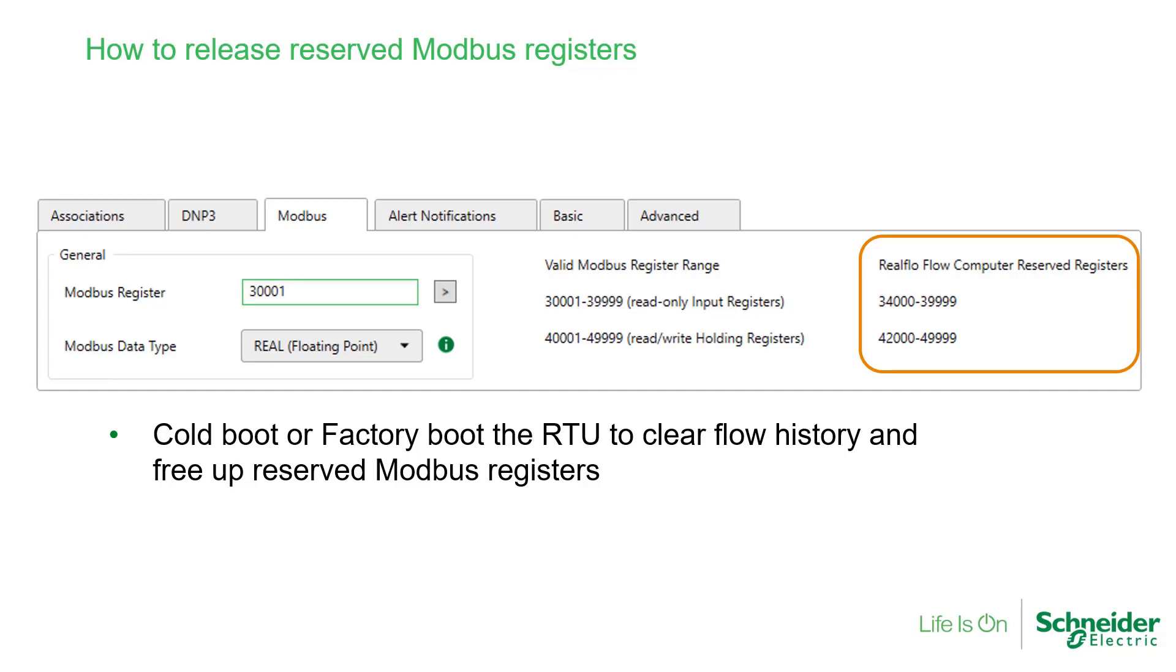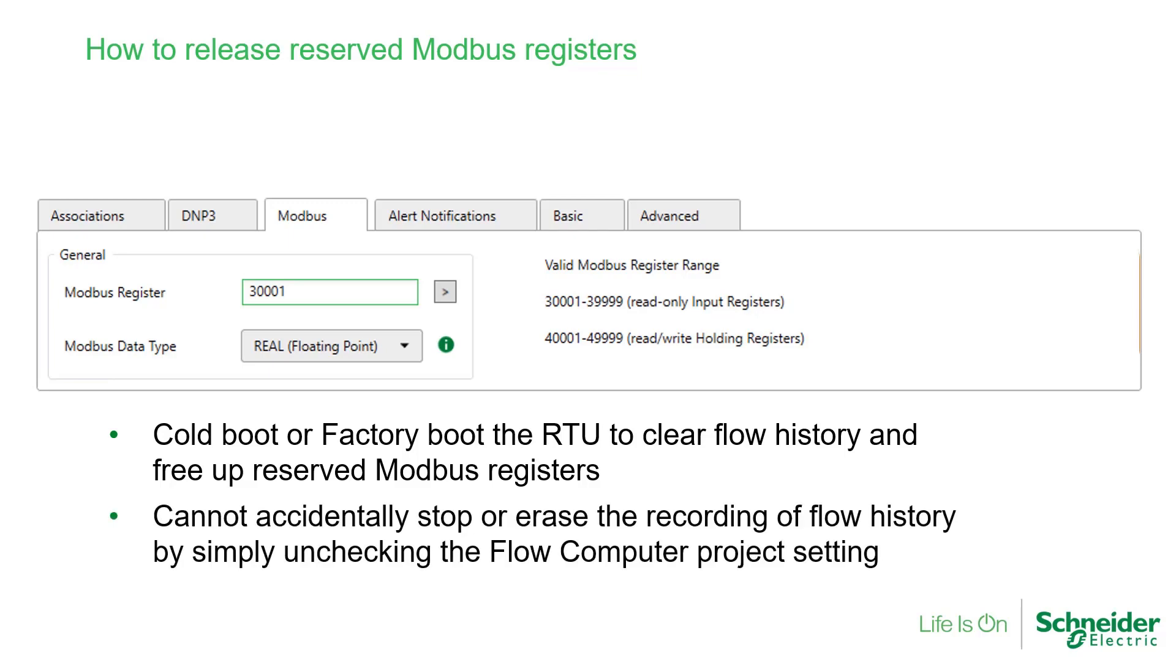You must cold boot and/or factory boot the X70 to accomplish this. This extra step is necessary so that a user cannot accidentally stop or erase the recording of flow history by simply unchecking the flow computer project setting and writing this to the RTU.